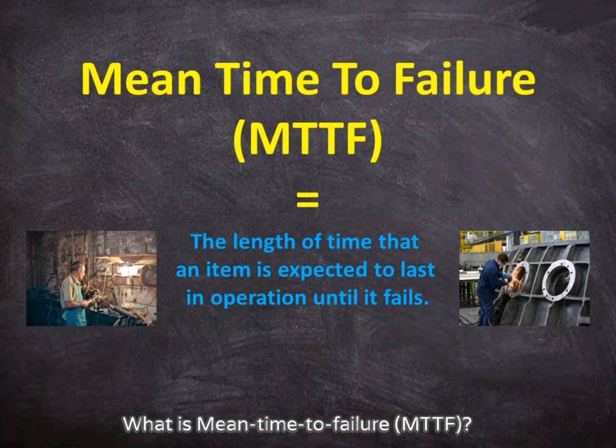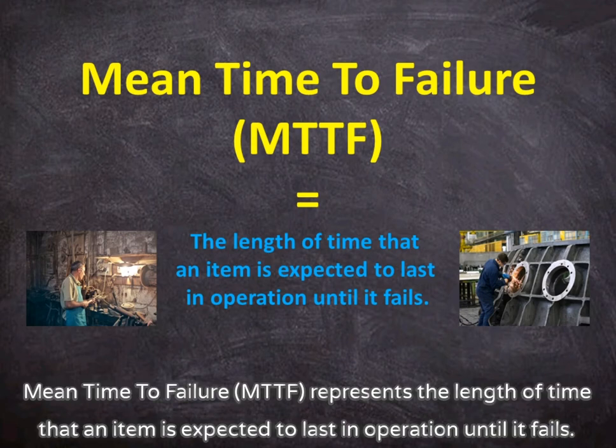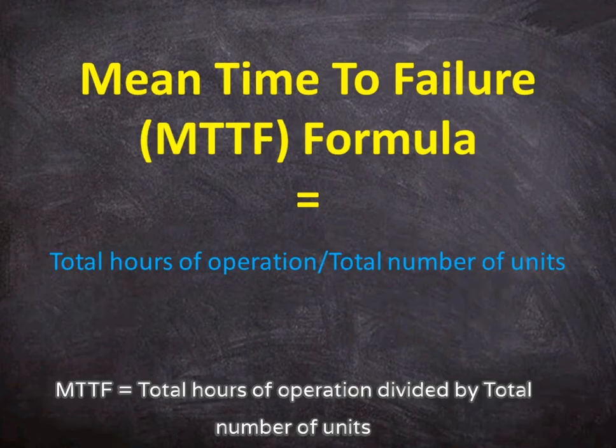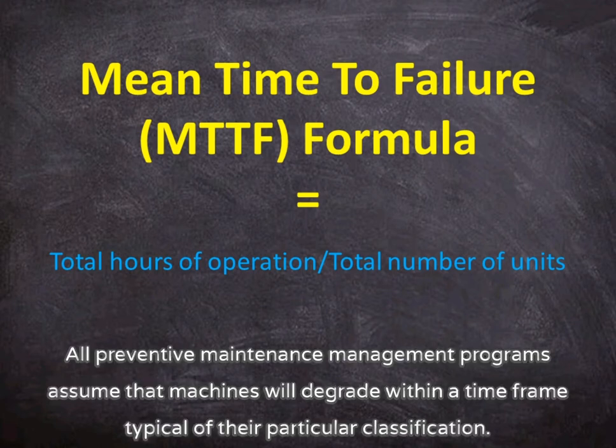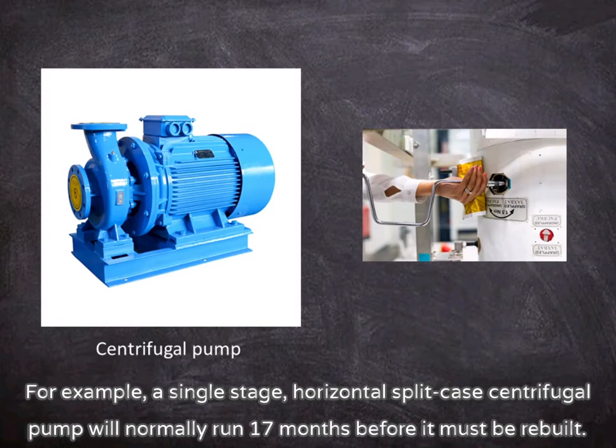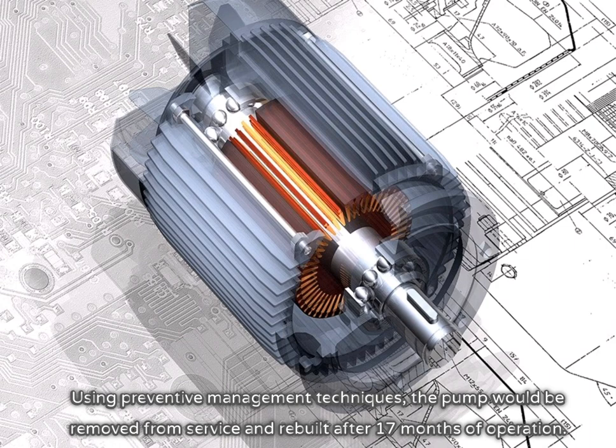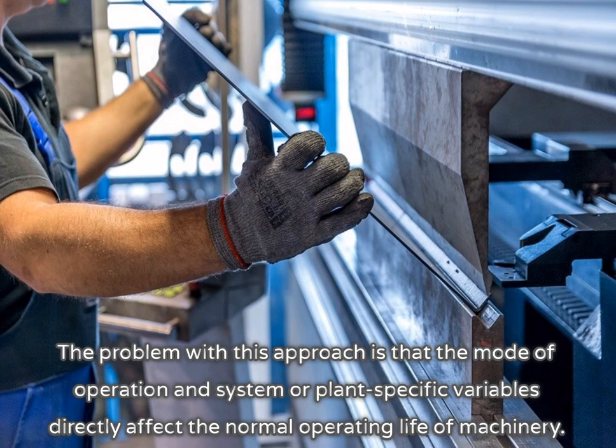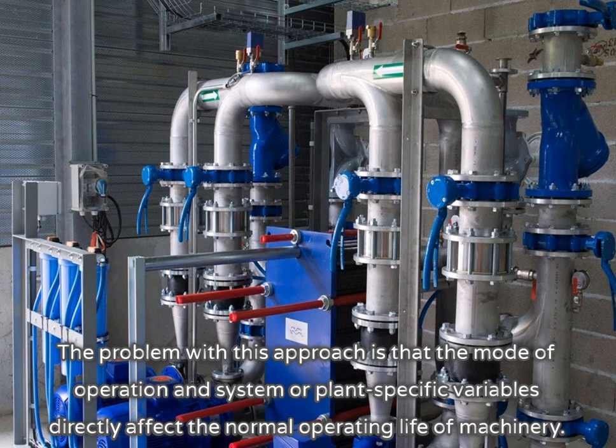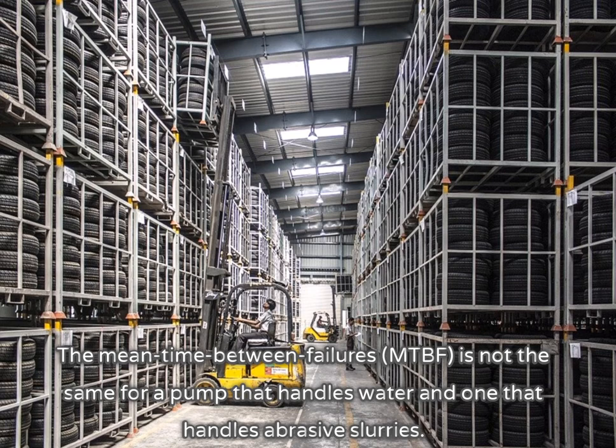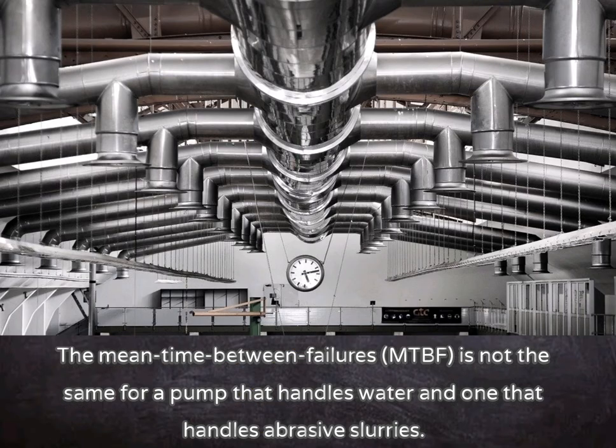What is mean time to failure MTTF? Mean time to failure MTTF represents the length of time that an item is expected to last in operation until it fails. MTTF equals total hours of operation divided by total number of units. All preventive maintenance management programs assume that machines will degrade within a time frame typical of their particular classification. For example, a single-stage, horizontal-split-case centrifugal pump will normally run 17 months before it must be rebuilt. Using preventive maintenance management techniques, the pump would be removed from service and rebuilt after 17 months of operation.